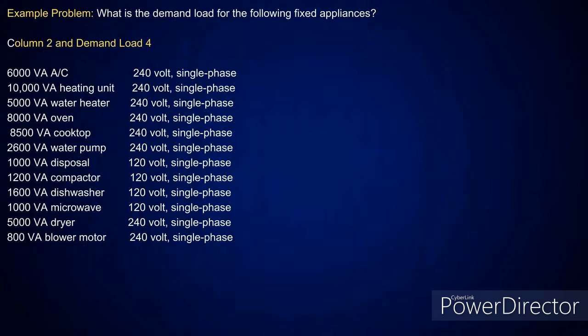Now, what I do here is I look at what gets removed from here. Well, we already did the dryer, didn't we? Yeah. Okay, dryer load goes. Okay, we did cooking equipment, it goes, right? There's a cooktop and oven. All right, now there's only 2 other things that are left here. And that's my non-coincident load between my heating and AC load. So those will drop. Everything else that's left there is going to be in the fixed appliance load.